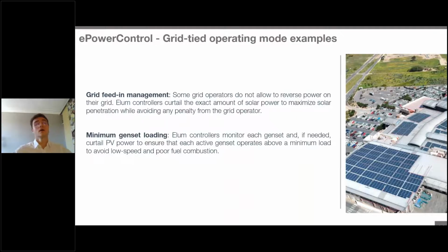Then we have, during blackouts, the gensets that are turned on to ensure that the correct energy flow is fed to the load. But the e-power control will be managing the inverters again to ensure that we have as much energy as possible produced thanks to the PV inverters, while ensuring that we always have this minimum genset loading on the genset side to ensure the safe management of your genset power plant.